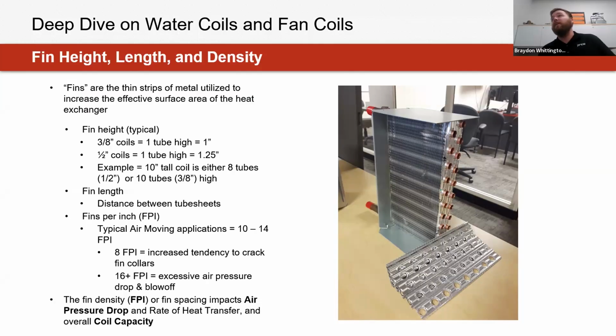And the first one being fins. Aluminum fins are going to be constructed in many different water coils that you would see in the industry. Essentially, this is where a lot of the heat transfer is going to occur from the air passing through that coil as the fluid passes back and forth through the coil itself. In terms of tubes, typically these are going to be 1/2-inch tubes passing through the coil.